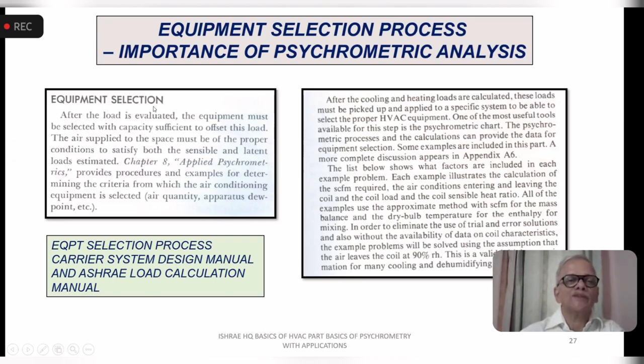Here you find equipment selection. This is the extract from Carrier. After the load is evaluated, the equipment must be selected with capacity sufficient to offset this load. You have done the load calculation, and now you have to select the capacity of the plant, which has to offset this load. The air supplied to the space must be of proper conditions to satisfy both the sensible and latent loads estimated. Now, there is chapter 8, applied psychrometrics, which provides the procedure and example for determining the criteria from which the air conditioning equipment is selected.